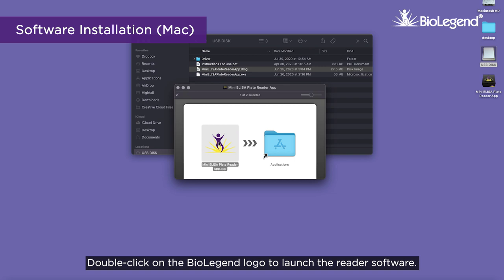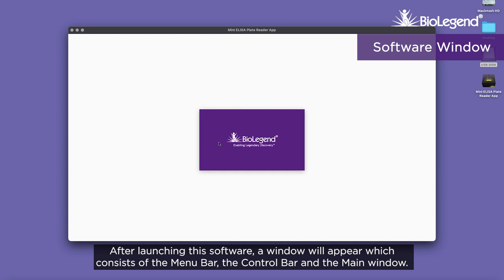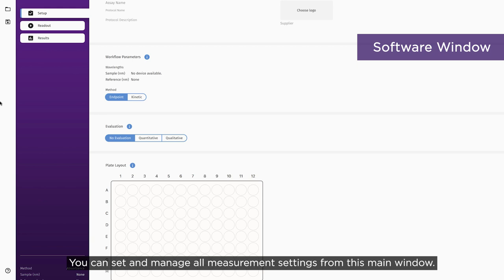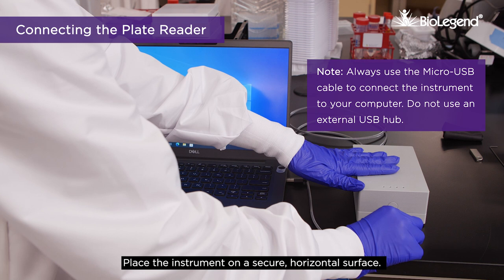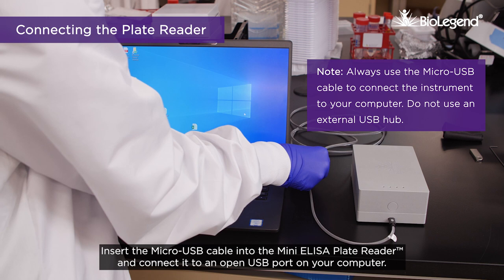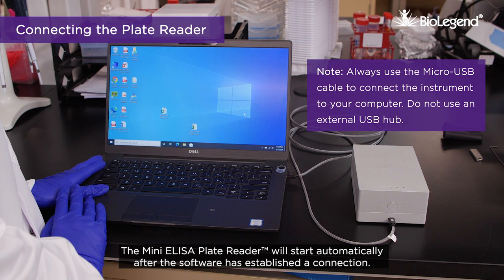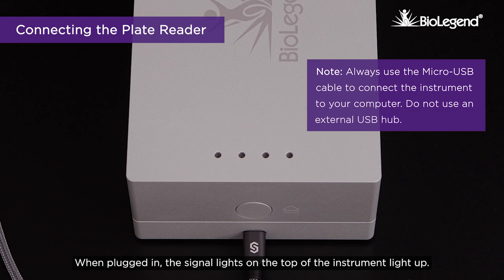After launching this software, a window will appear, which consists of the menu bar, the control bar, and the main window. You can set and manage all measurement settings from this main window. Place the instrument on a secure horizontal surface. Insert the micro USB cable into the Mini ELISA Plate Reader and connect it to an open USB port on your computer. The Mini ELISA Plate Reader will start automatically after the software has established a connection. When plugged in, the signal lights on the top of the instrument light up.